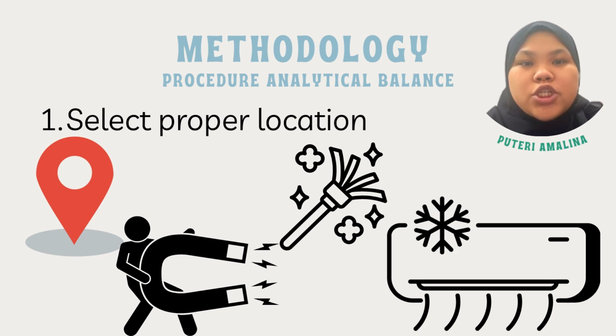We're moving to the procedure to use an analytical balance. Firstly, we have to select the proper location. We have to avoid direct sunlight, choose a stable and horizontal location that is dust-free, refrain from touching magnetic or magnetic field generating objects, and keep clear of air currents produced by ventilators, air conditioners, and open windows. Next, leveling the analytical balance. On the level adjustment feet, it has an air bubble indicator where it shows if the analytical balance is leveled to account for any slight deviations or tilts.